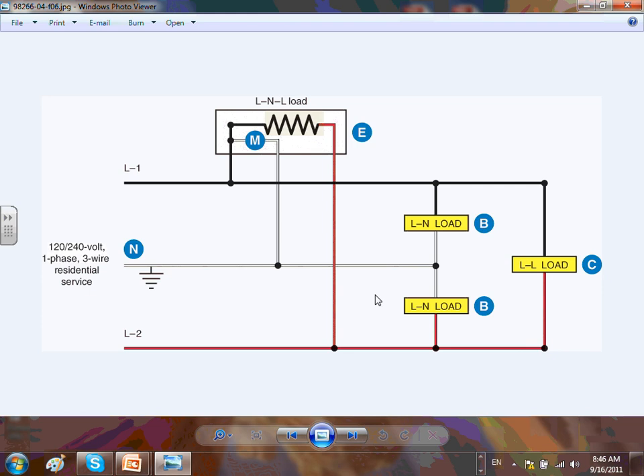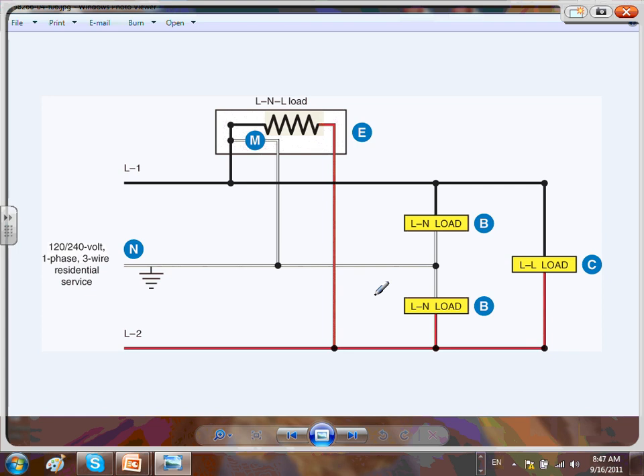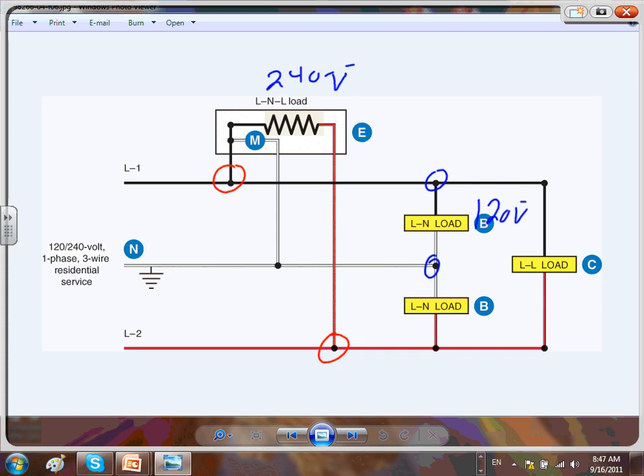In residential, if you don't understand this circuit, you will be confused — even in commercial. In the US, there are two types of voltages brought to residential: 120 and 240. You can connect equipment at 120 or 240. This equipment here is 240 for a ventilator, and you can connect from line to neutral to get 120 volts. The 240 volt connection goes from phase to phase. The difference between loads: one load needs a neutral and one does not.